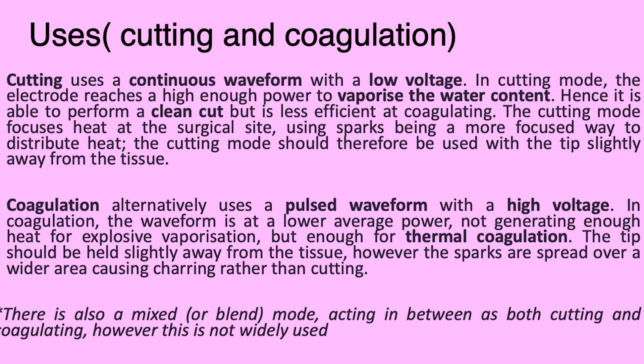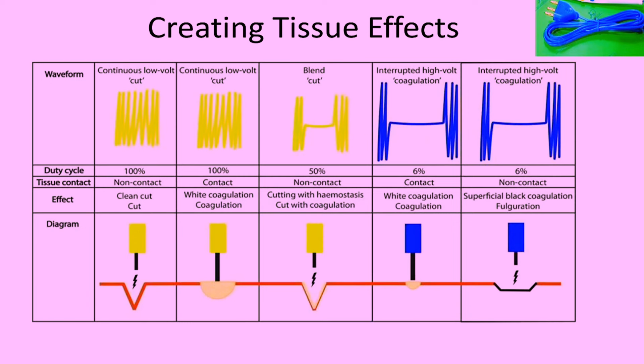In blend mode, it has an interrupted waveform, allowing for slower cutting and coagulation at the same time, creating a combined tissue effect. This is the electrosurgical pencil — you can see the yellow and the blue button. The yellow activates the cut function and the blue activates the coagulation function. Cutting mode has a continuous frequency with low voltage — not as high as coagulation mode — and is active 100% of the time.